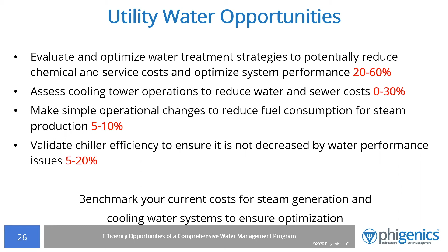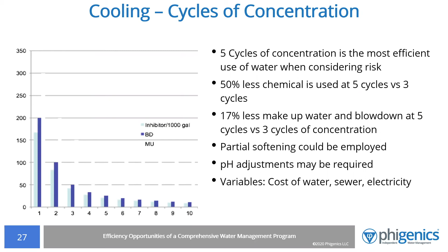Cycles of concentration, or in other words, how many times water flows around the cooling tower loop before it is dumped to waste. You want to optimize the use of water while taking into consideration the cost of water, sewer, chemicals, energy, and service hours, while ensuring that you are not jeopardizing the lifespan of the equipment. We see far too many systems where facilities are spending 2 to 3 times as much as they should be on cooling tower operations. Biocide strategy.